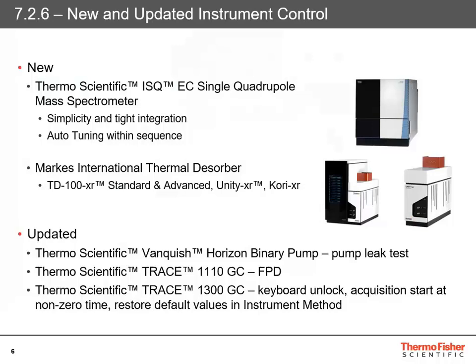This is a native Chromeleon driver — the first mass spectrometer to be delivered with a native Chromeleon driver. It has very tight integration with Chromeleon, enabling operational simplicity for this mass spectrometer. The auto-tuning for the mass spec is now contained within the sequence, so all of that is done from within Chromeleon. Many of the features released with 7.2.6 have also been released with this mass spectrometer in mind.